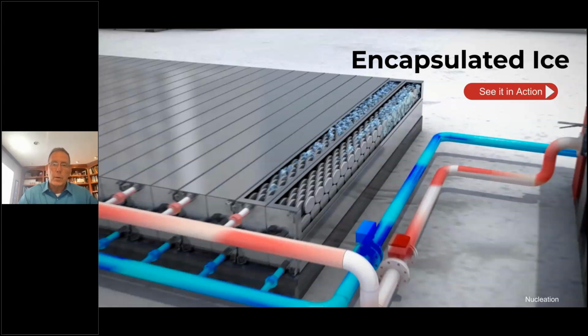Although that can be propylene glycol, which is pretty organic too. The ice inside the capsules freezes at around 28 degrees. Historically, with large clunky tanks, you have to get it down to around 22 degrees. So it's less work on the chillers to make ice.